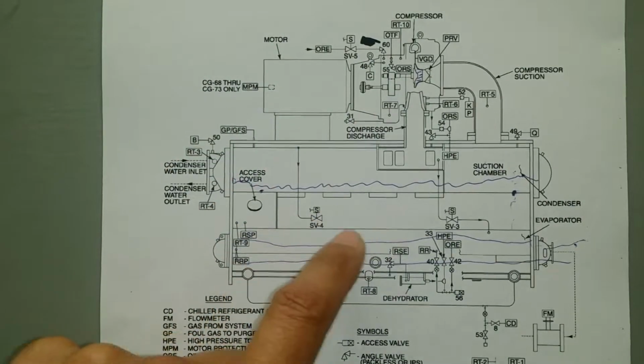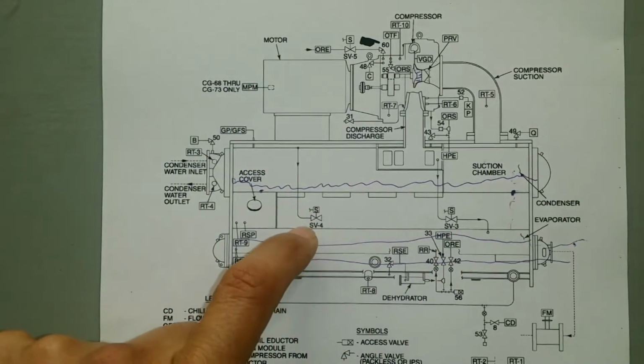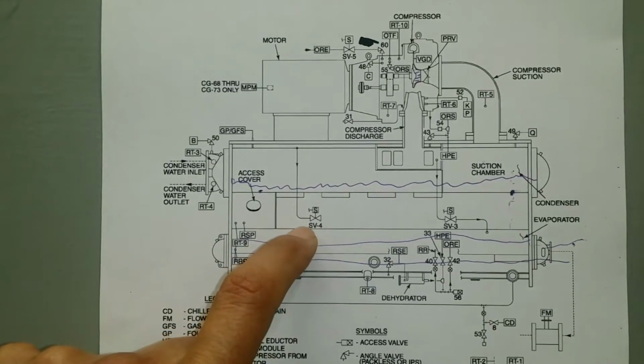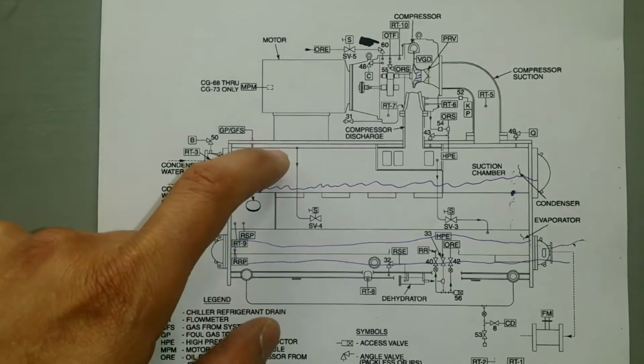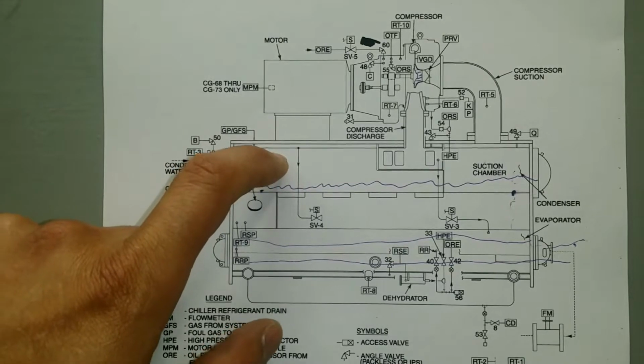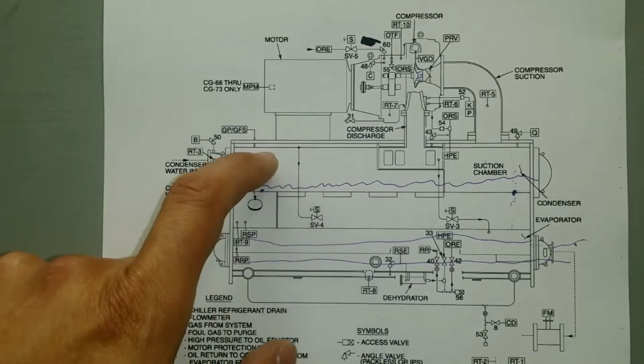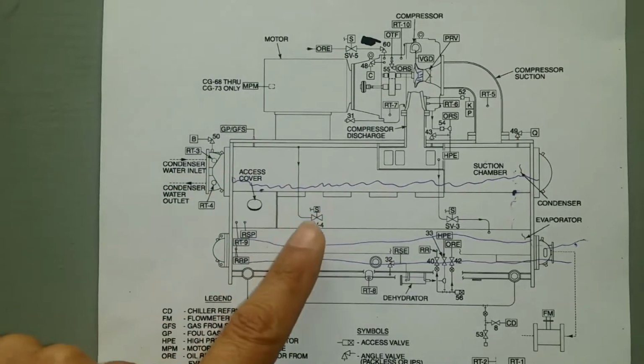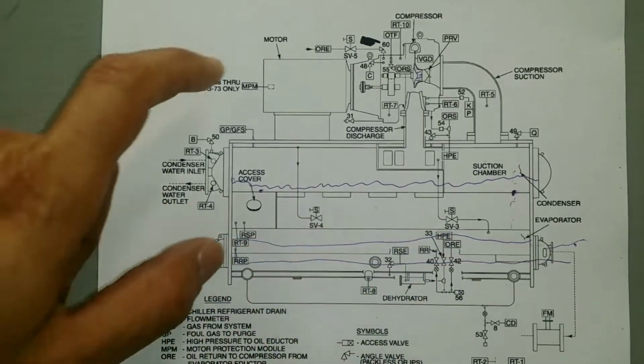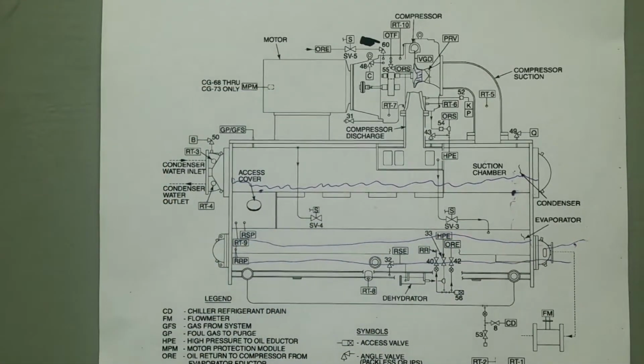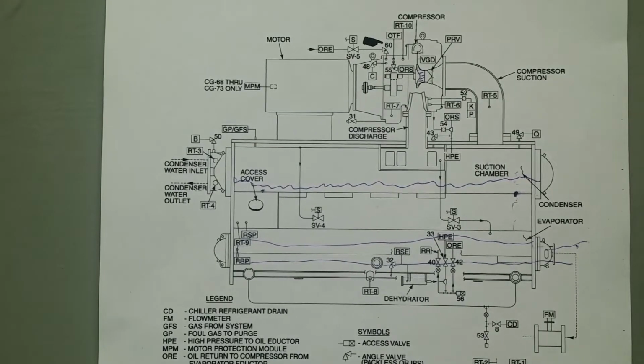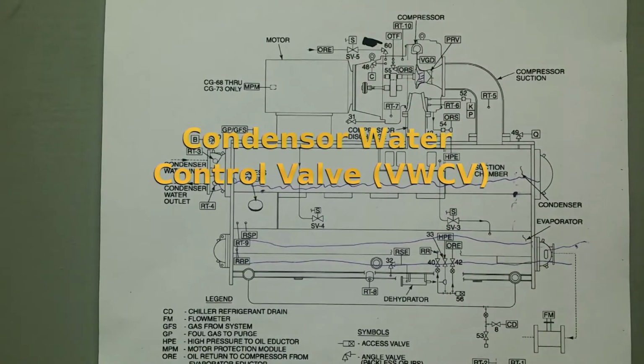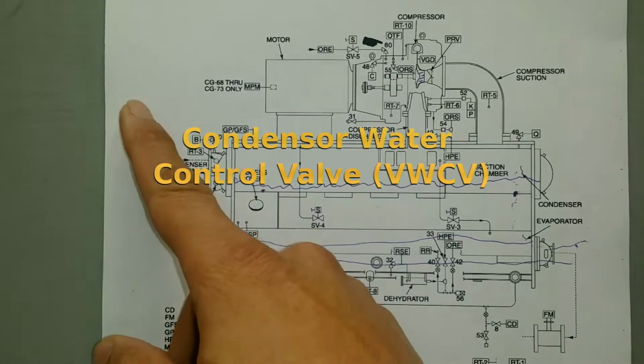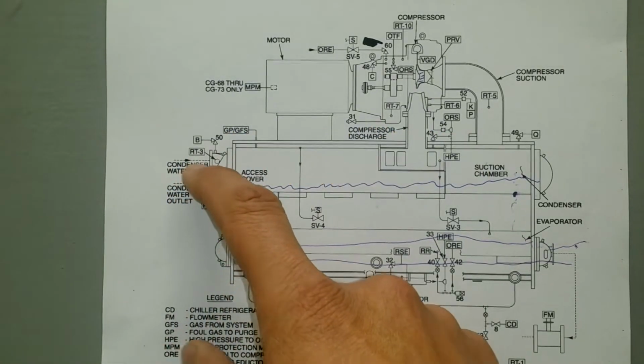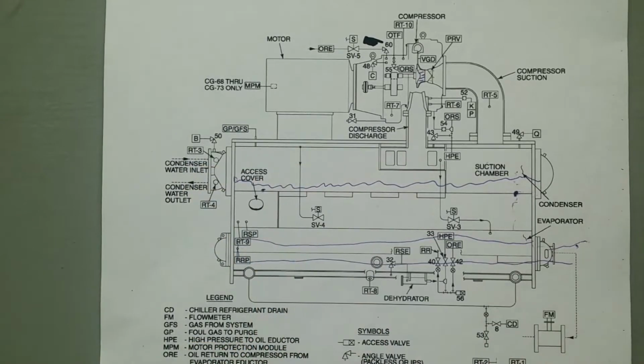Also, here to the side, we have these hot gas bypass valves, and what they do is take some of the gas that was over here at high pressure and bypass it straight from the condenser into the evaporator. That needs to be done only during light load operations. Lastly, I want to make you aware that there is a condenser water control valve, which determines how much water will be going into the condenser.